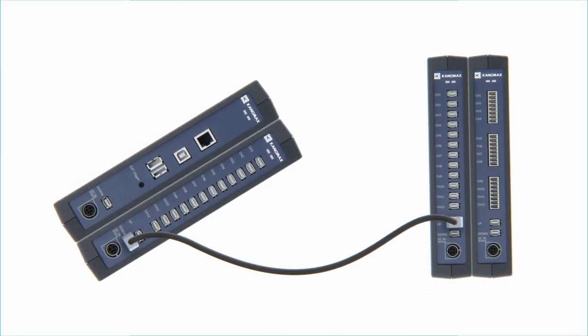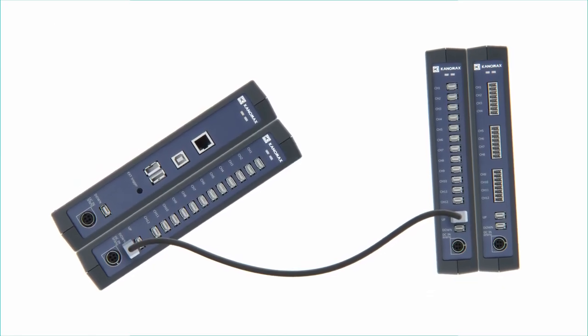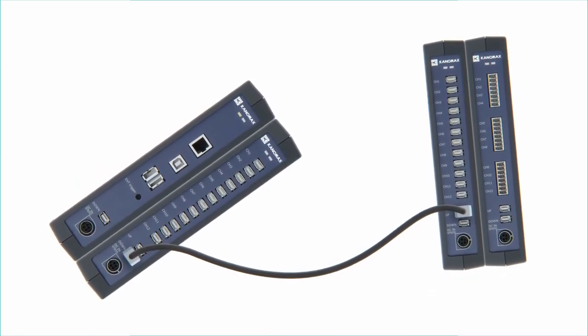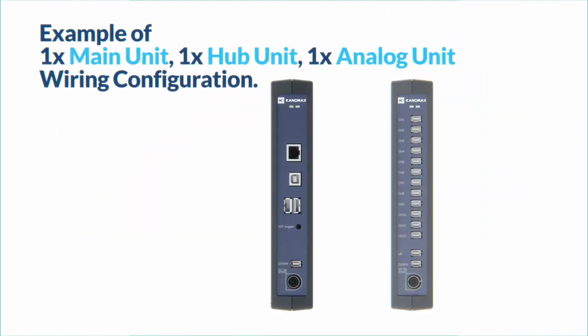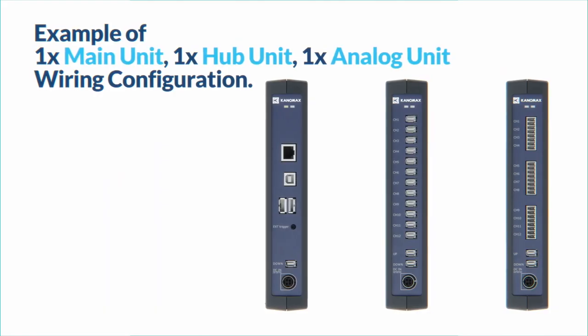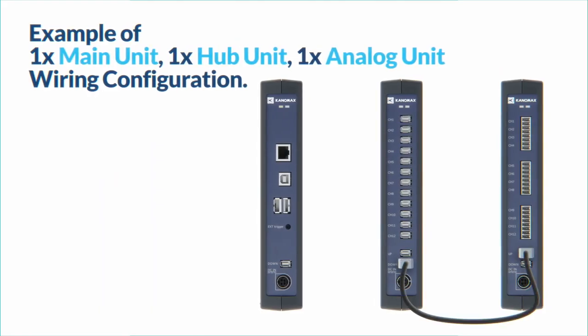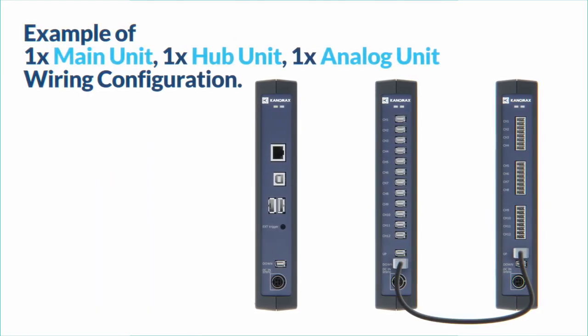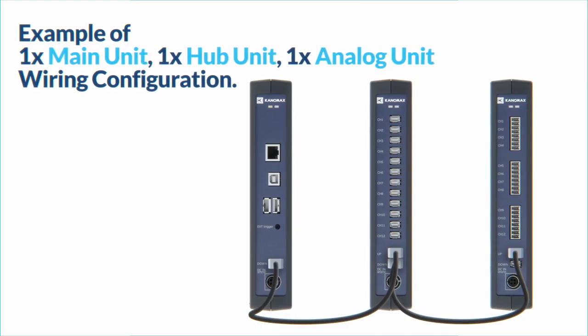using the standard cable. When linking units via standard cables, it's important that you connect them in an order similar to what was mentioned before. In a configuration that uses a single main unit, hub unit, and analog unit, connect the analog unit's up terminal to the down terminal of the hub unit. Then connect the up terminal of the hub unit to the down terminal of the main unit.